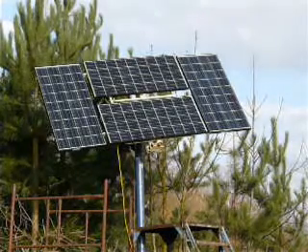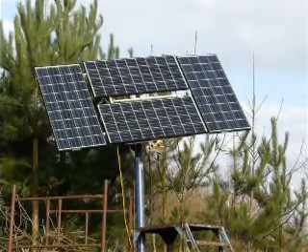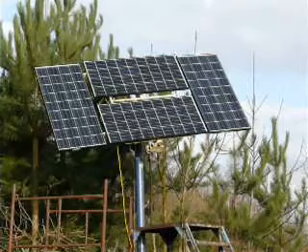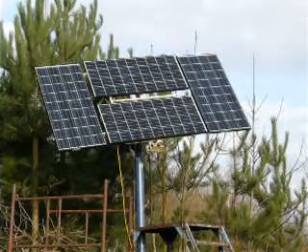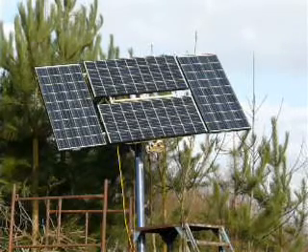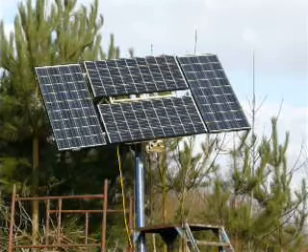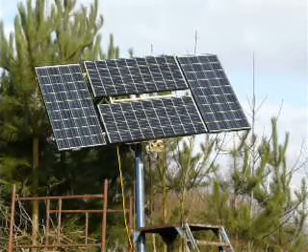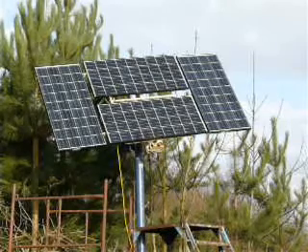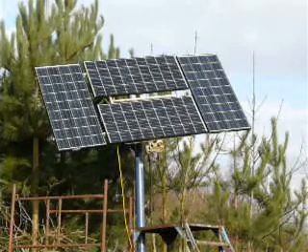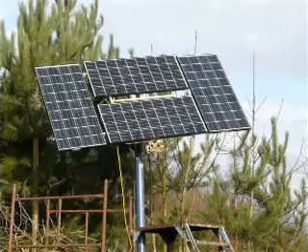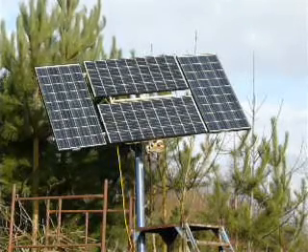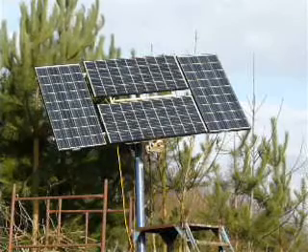This array is designed to track the sun, and this is important as the panels work most efficiently when facing directly towards the sun or 15 degrees either way. For this latitude, i.e. in Britain, there's a marked difference in solar radiation between winter and summer, and for this reason the tracking can give up to 50% greater output in summer, but is only a marginal benefit in the depths of winter.